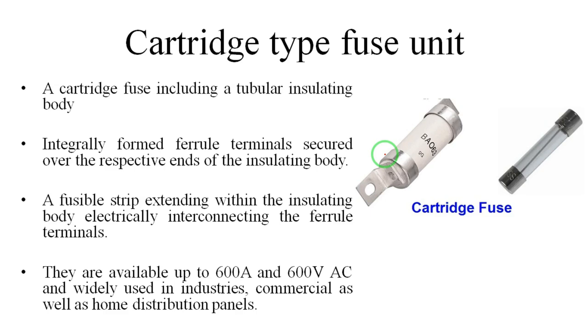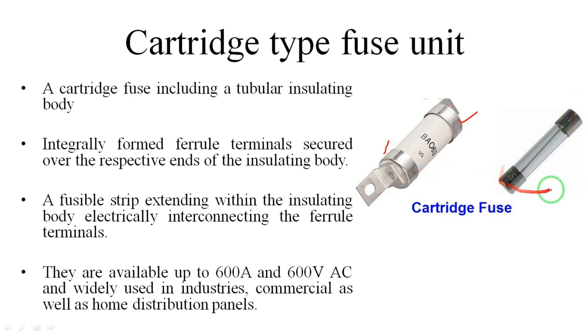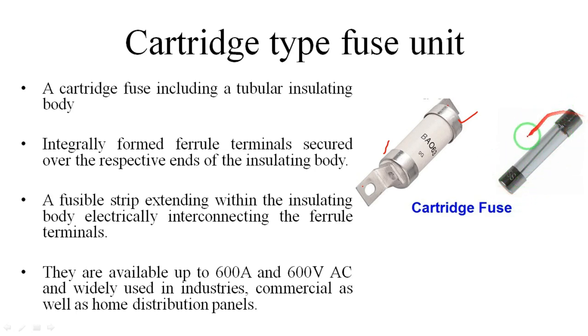The next type is the cartridge type fuse. This type of fuse has a tubular insulating body with two end caps — a front end and a back end — and two connectors. In the center there is a wire called a strip or melting wire. This wire is made up of a fusible strip which is connected to the front and back ends. When overcurrent flows from one side to the other, it melts easily and the circuit becomes open.